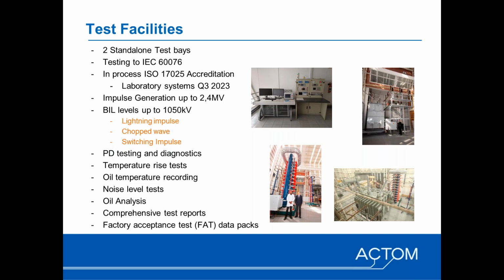We can impulse test up to 1050 kV lightning impulse, with the capability of loading the impulse generator to 2.4 million volts. We do PD testing, temperature rise tests, oil tests, noise level tests, and all other required tests, then put all of this together for you in a data pack.